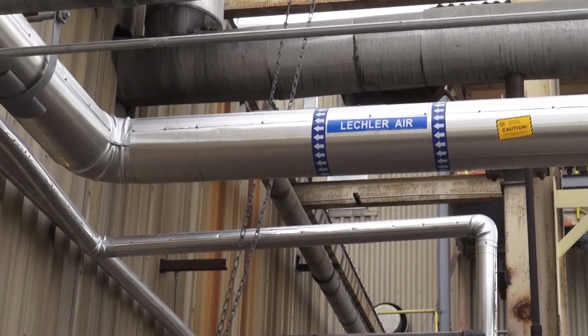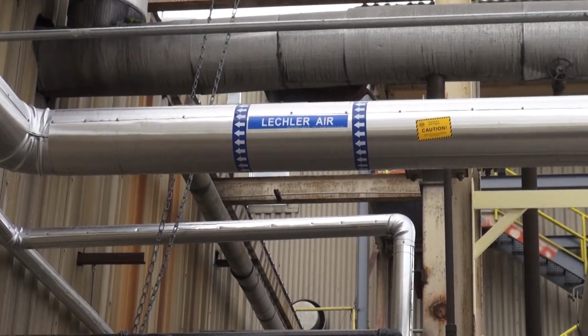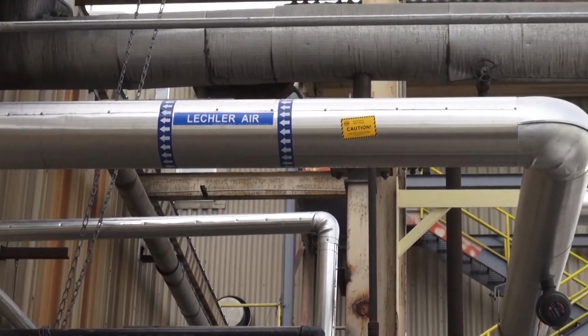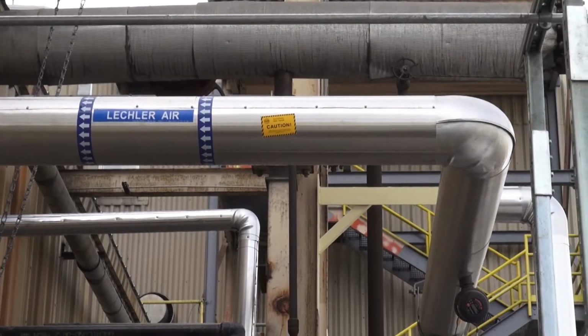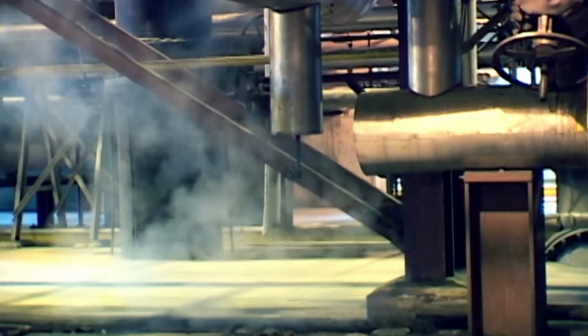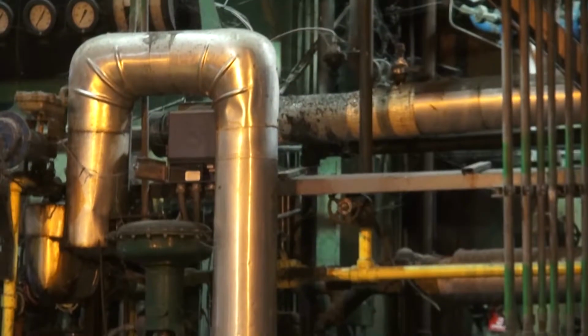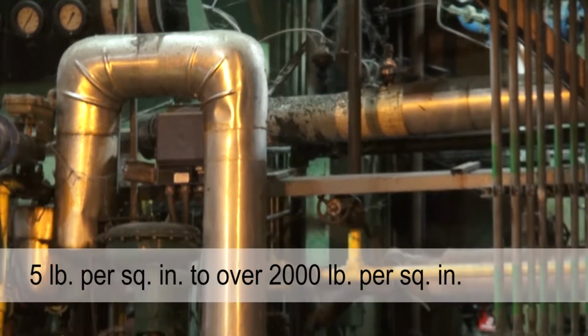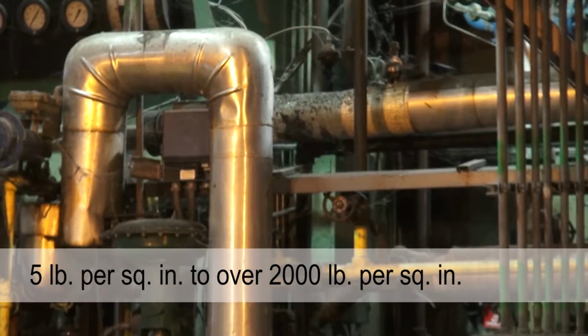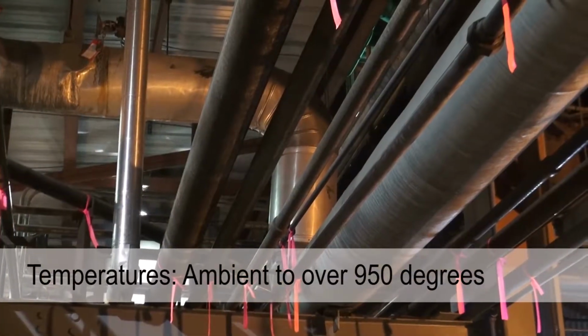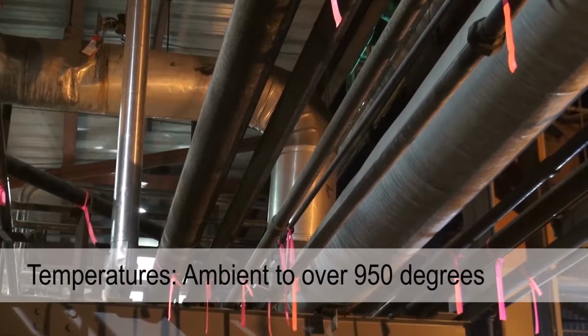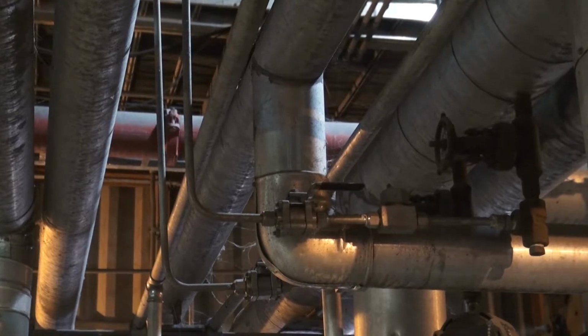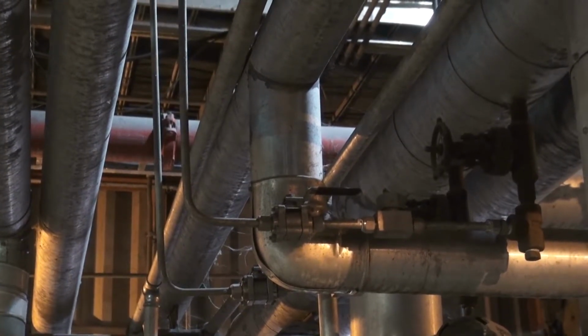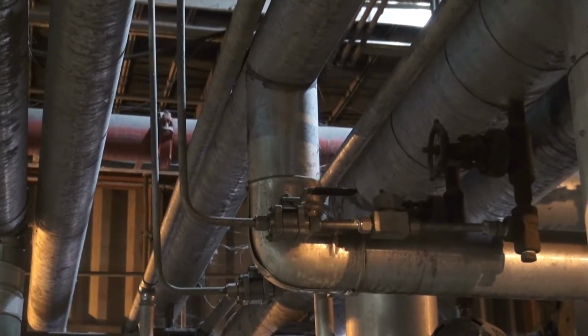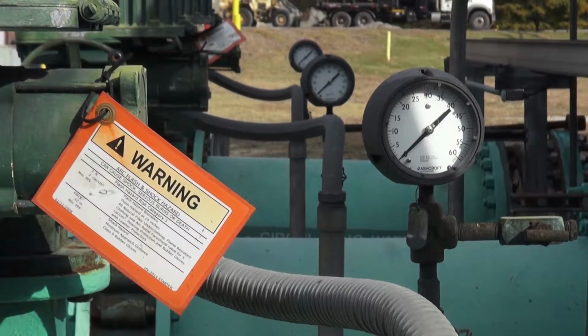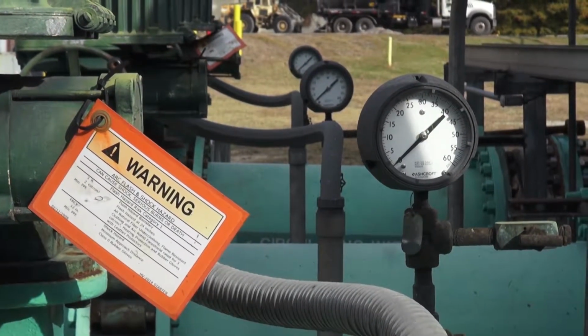A combination of high-pressure and temperature-processed piping containing air, fuel, water, and steam is used to produce electricity in the plant. Steam is used throughout the plant and is the main force that turns the turbine generator. Pressures range from as little as 5 pounds per square inch to over 2,000 pounds per square inch, with temperatures ranging from ambient to over 950 degrees Fahrenheit. Most piping that can cause thermal injuries is insulated, but there are still exposed metal components that can cause serious burns. Do not touch or grab any non-insulated piping or valves without first knowing its temperature.